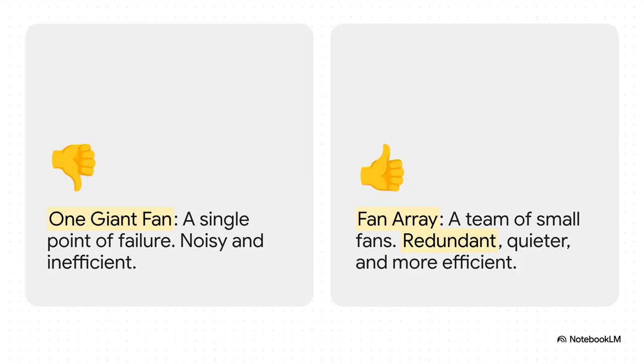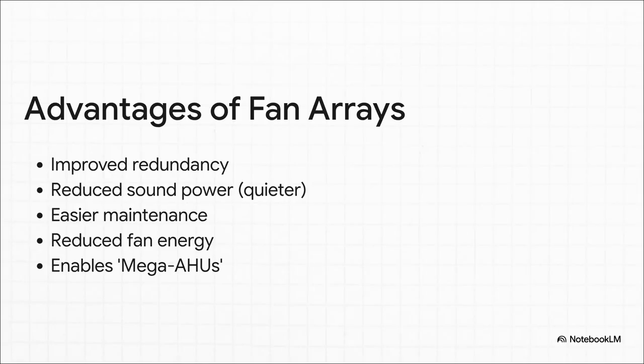Okay, let's talk about the fans. For years, buildings used one single giant fan. This created a huge risk, right? If that one fan failed, the whole building's ventilation system went down. The new approach is the fan array. Think of it as a coordinated team of smaller, smarter fans all working together. And the advantages here are huge. If one of the small fans in the team fails, the others just speed up a tiny bit to compensate. Nobody even notices. They're also much quieter, and replacing a small fan is a simple one-person job. This design is what allows for these massive, ultra-efficient, mega air handling units in really big buildings.